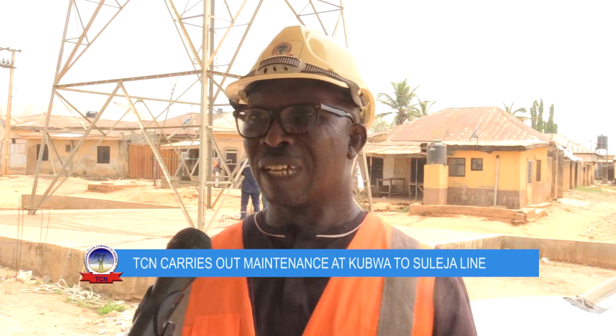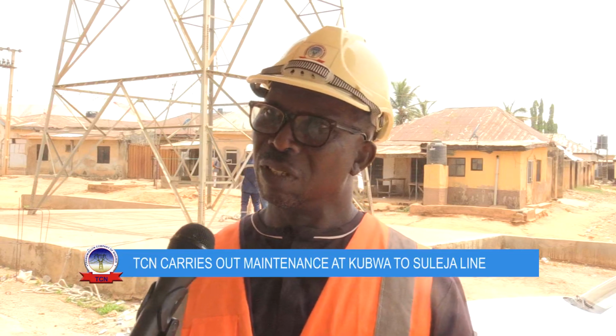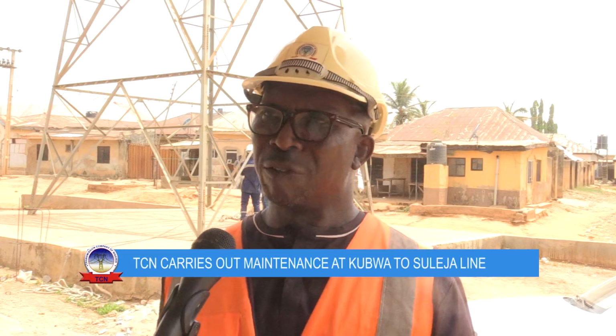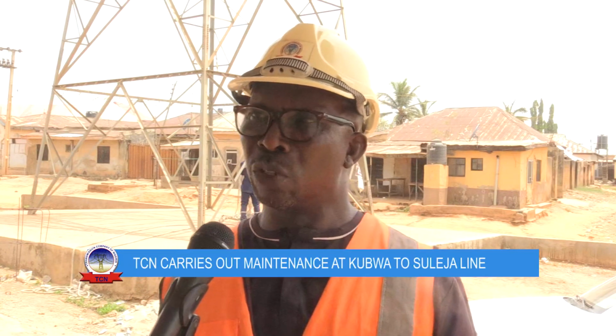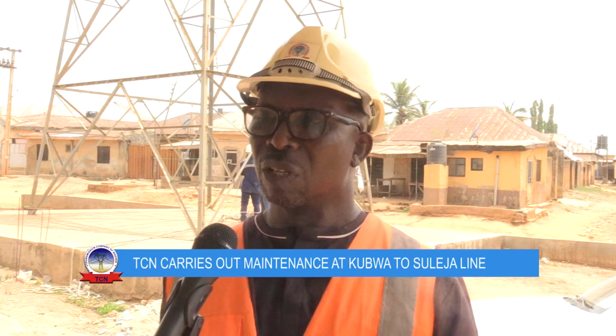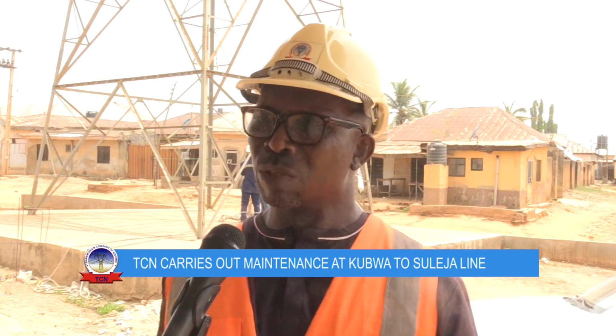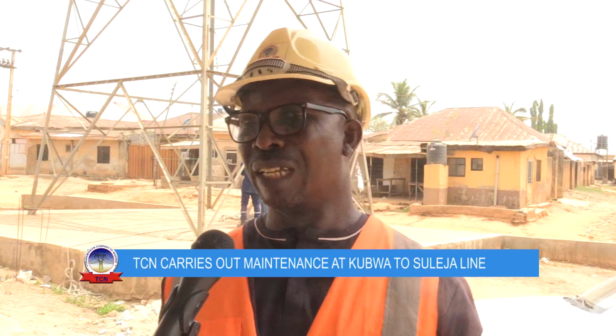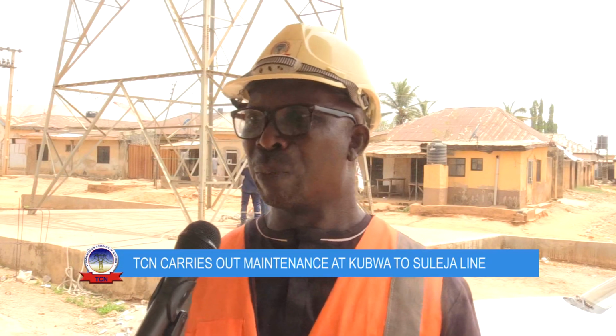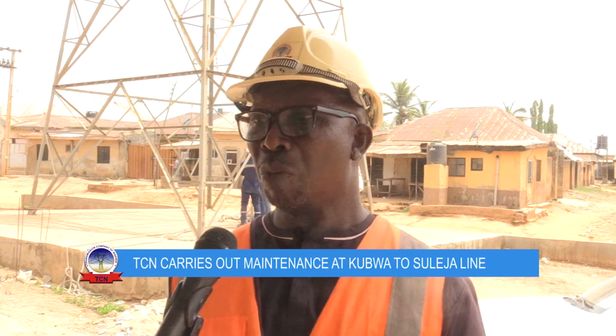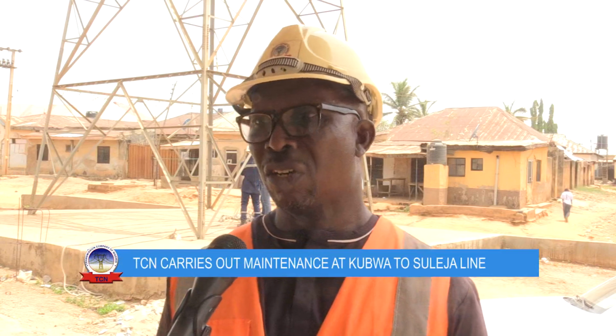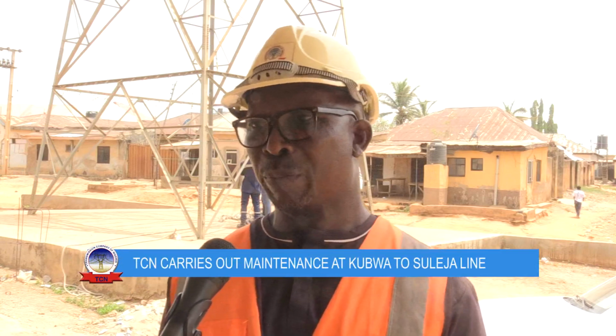Presently, it has not affected the transmission system, but if we had allowed this and it cut tomorrow, that would mean the whole of Suleja, Kubwa and Evaro would be in blackout until we replaced this jumper cord. But due to our immediate response, I think we saved a lot of megawatts, and there was no load loss as such.